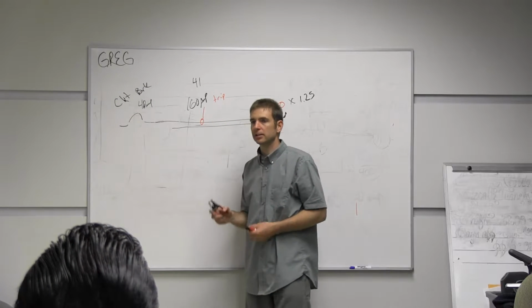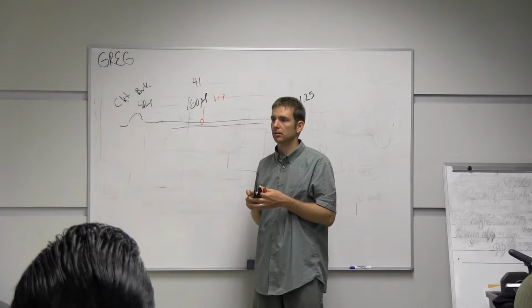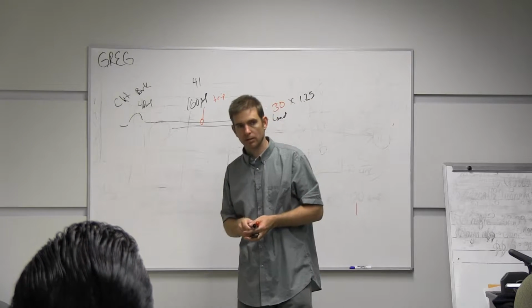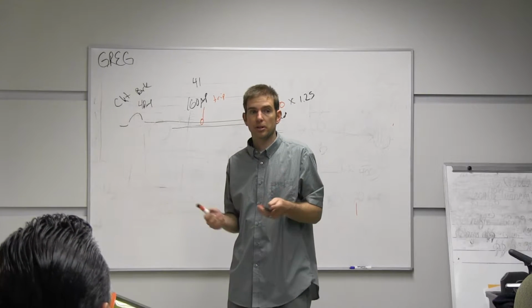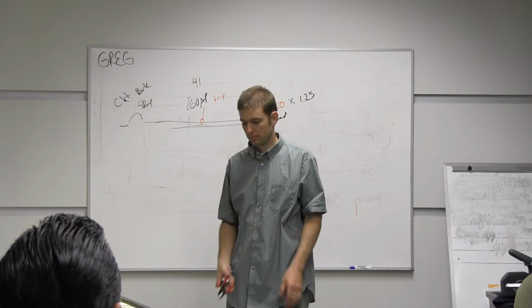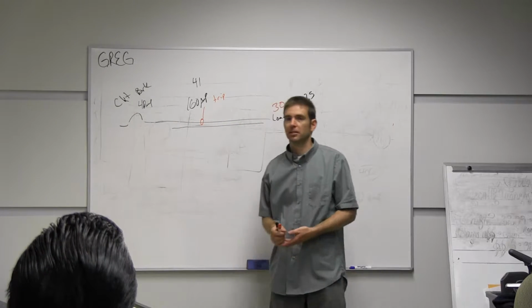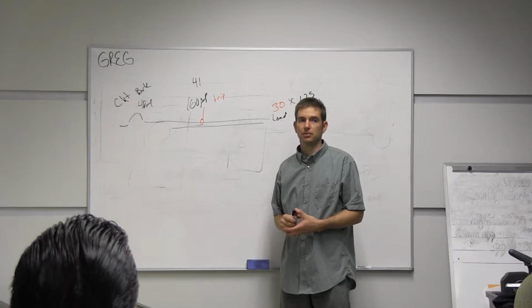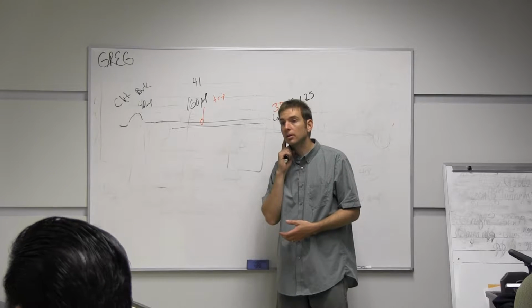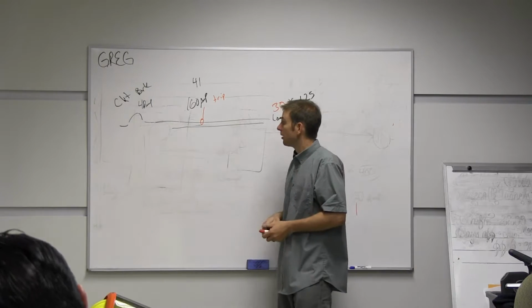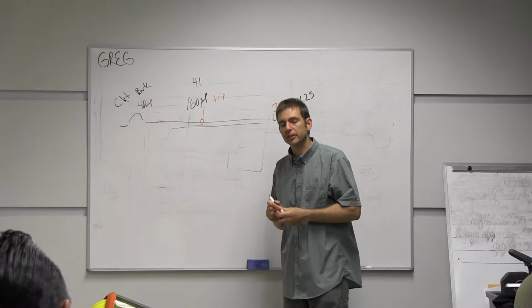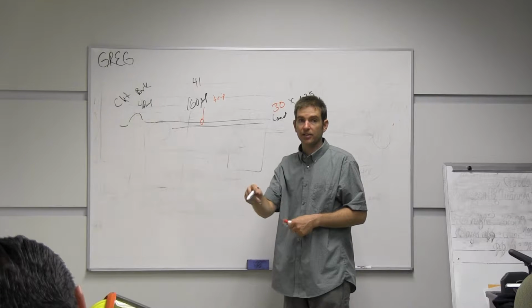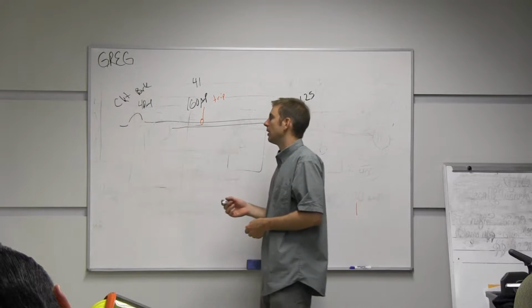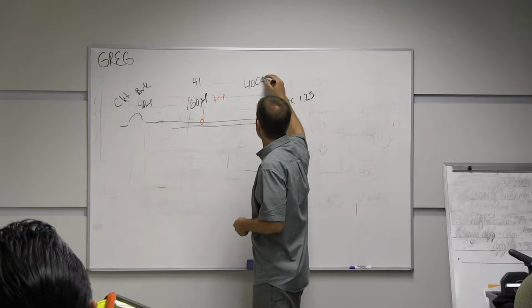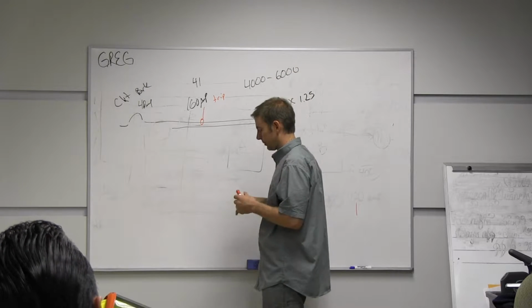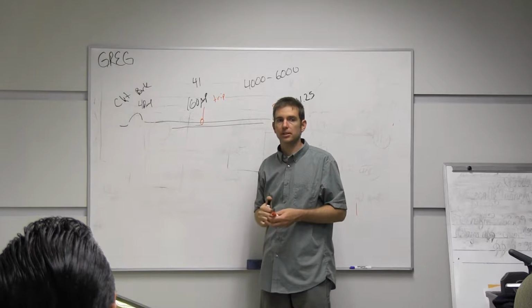And how many amps do you think it takes to burn a hole through steel that big on this much surface area? Very high amperes. Probably pretty high. How much do you think? Would it be 40 amps? Depends on your tool. It tripped the circuit breaker, but it burned my tool. That is a short circuit, so more than 40. Definitely more than 40. It depends on the distance of the tool, I think. It depends on a lot of factors. Generally, when you blow a hole of the size and surface area that I talked about, it's going to be about 4,000 to 6,000 amps.